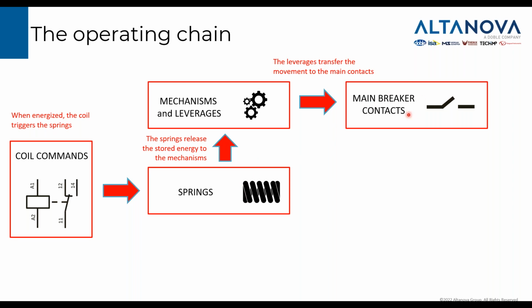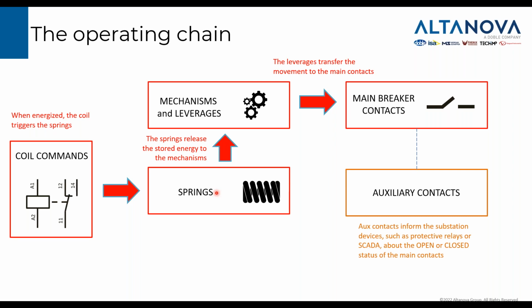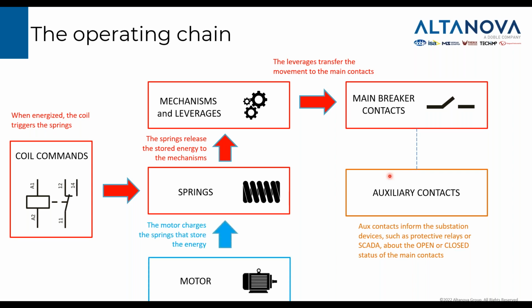The status of the circuit breaker is monitored through auxiliary contacts. For example, protection relays and SCADA systems know about the main contact position through this kind of auxiliary contact. So these are parts of the breaker that need to be tested, because if there is a problem on the auxiliary contacts, then all the devices in the substation will not get the right information and cannot take the right decision.